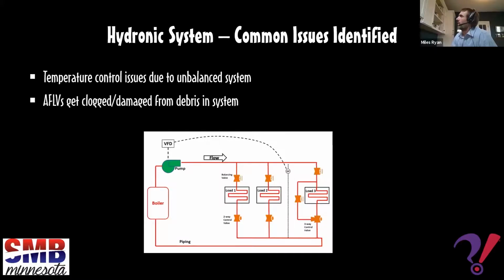Thanks, Mark. So some of the issues often related to the TAB process being brought in too late or not being completed at all would be temperature control issues with an unbalanced system. So a building I'm working in right now, a few years back, our firm got brought into that building because none of the units on the bottom floors of a high-rise residential were ever getting any heat out of their fin tube radiation, but everyone on the top floors was fine.